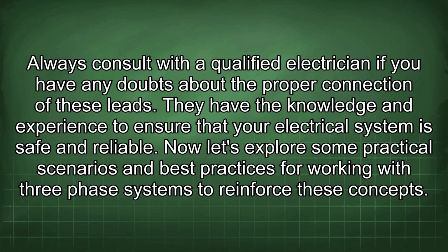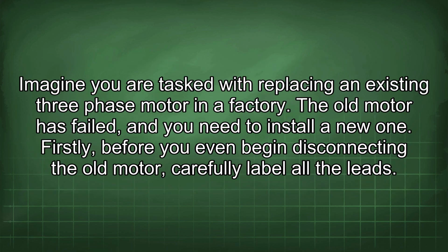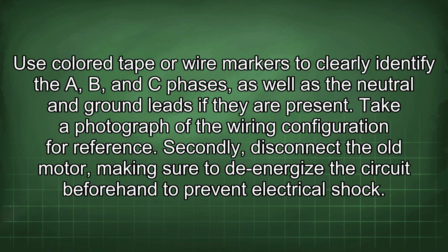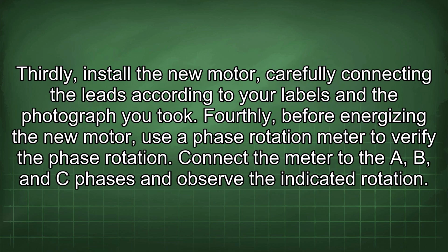Now let's explore some practical scenarios and best practices for working with three-phase systems to reinforce these concepts. Imagine you are tasked with replacing an existing three-phase motor in a factory. The old motor has failed and you need to install a new one. Firstly, before you even begin disconnecting the old motor, carefully label all the leads. Use color tape or wire markers to clearly identify the A, B, and C phases, as well as the neutral and ground leads if they are present. Take a photograph of the wiring configuration for reference. Secondly, disconnect the old motor, making sure to de-energize the circuit beforehand to prevent electrical shock. Thirdly, install the new motor, carefully connecting the leads according to your labels and the photograph you took.